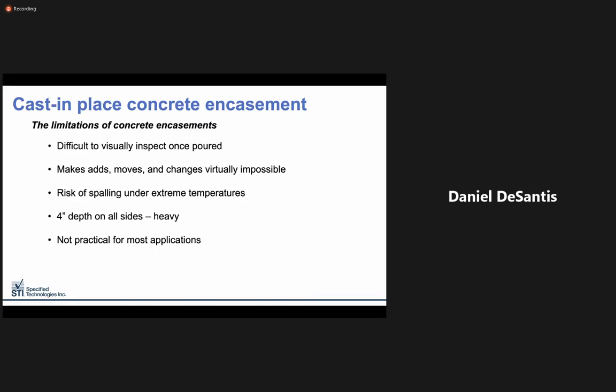As we can see, cast in place is not without its limitations. Concrete encasement is difficult to inspect, impossible to re-enter without demolishing, and carries the risk of spalling before fully cured. 4-inch encasement is just not practical for most applications due to its weight and labor-intensive installation. Great for some applications like rated barriers, but for thermally protective enclosures, it's less than ideal.